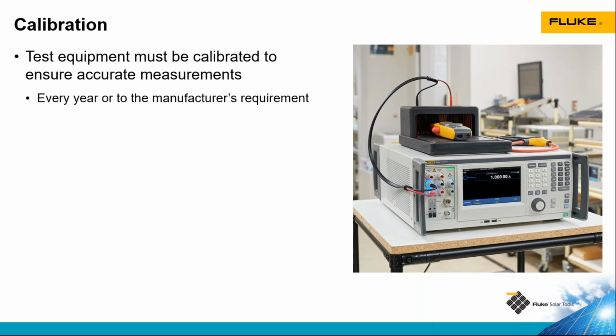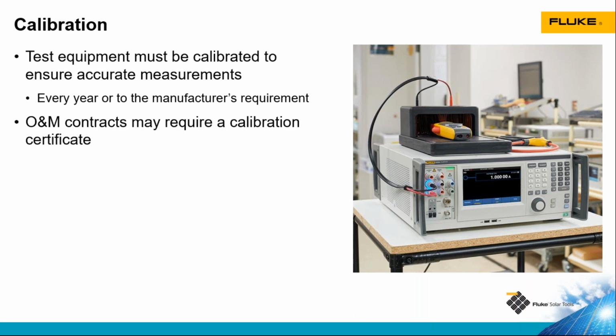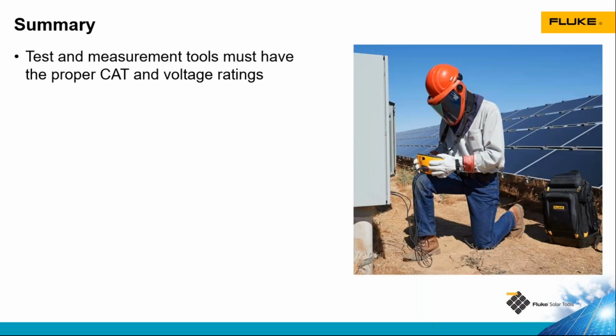We also need to calibrate our equipment. Fluke recommends an annual calibration for all of our tools, making sure that the tools are giving accurate results, so we're getting good test and measurement data. Some O&M contracts, especially if you're doing inspections when the system is being sold, will require a certificate of calibration. That's a special certificate that you can get to show that the tool has been calibrated to certain standards, and it has the date of the calibration, so they know they're getting good test results.